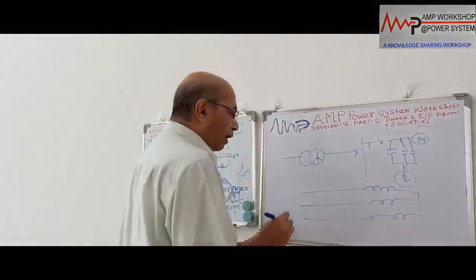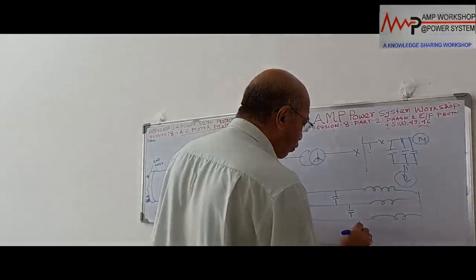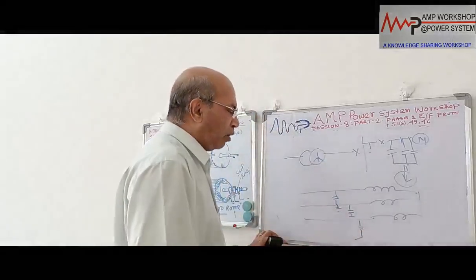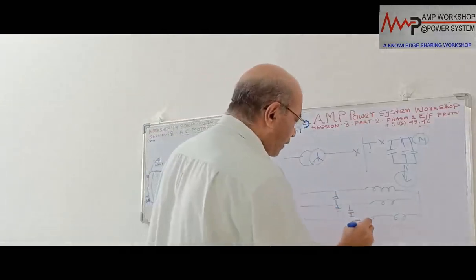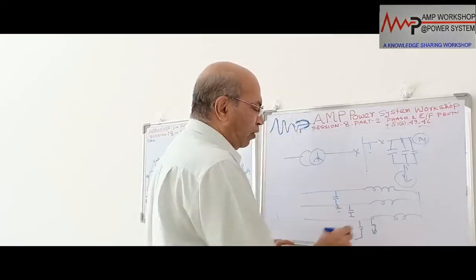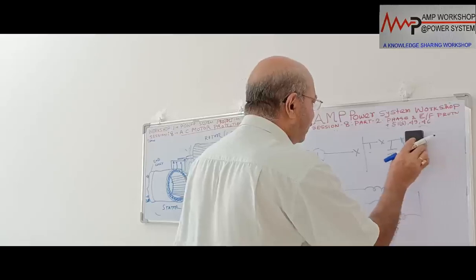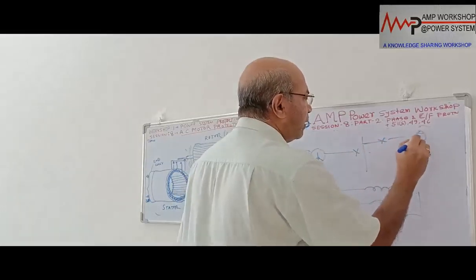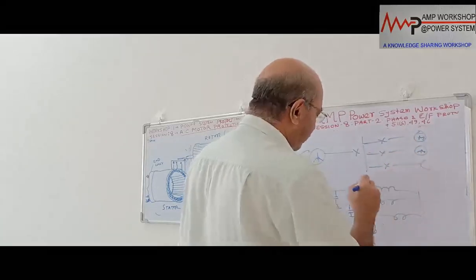Now in this motor, there is a continuous capacitance for each phase to ground, through which the charging current is flowing. And when we put this earth fault relay, the earth fault setting is more than the charging current. Now, if one of the phases got grounded over here, then this charging current will automatically be high. The switchgear has not only one motor, multiple motors are connected. One motor is connected over here, another motor is connected over here, and another motor is connected. All the motors are in the same sequence.